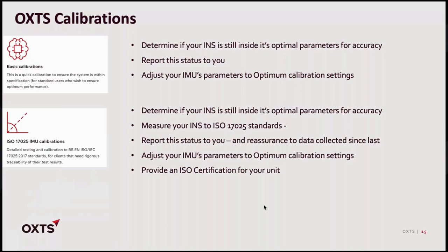But on top of that, you're getting two extra important things. One is an ISO certification that we send to you, so you've got evidentiary proof that you are within the ISO 17025 standards. And the second thing it provides, if this is important depending on how you're using our systems, is a clear understanding of any of the data, trials, anything that you've collected with that system since the last time it returned to home base. The certification is, again, proof that all of that data has never left outside of the accuracy required by the ISO standard.